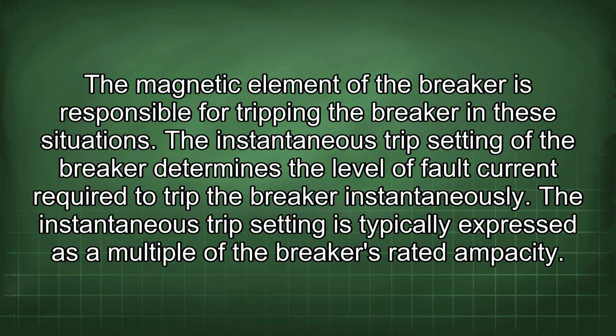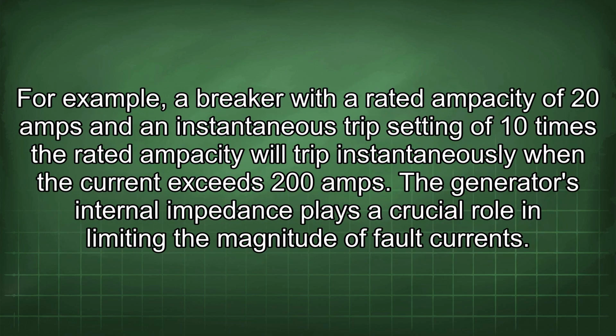The instantaneous trip setting of the breaker determines the level of fault current required to trip the breaker instantaneously. The instantaneous trip setting is typically expressed as a multiple of the breaker's rated ampacity. For example, a breaker with a rated ampacity of 20 amps and an instantaneous trip setting of 10 times the rated ampacity will trip instantaneously when the current exceeds 200 amps.